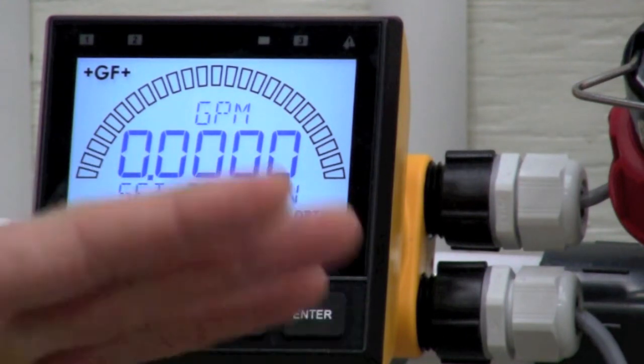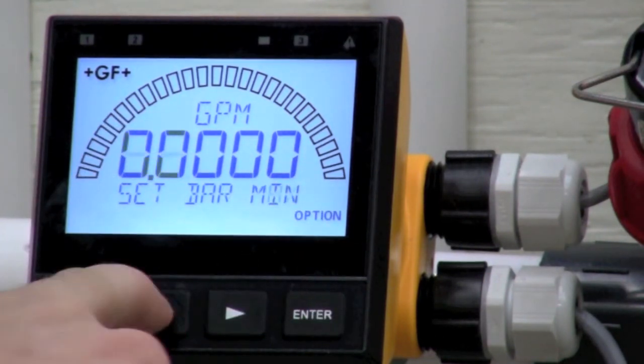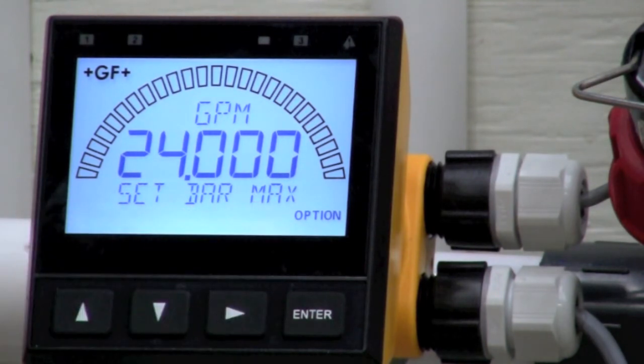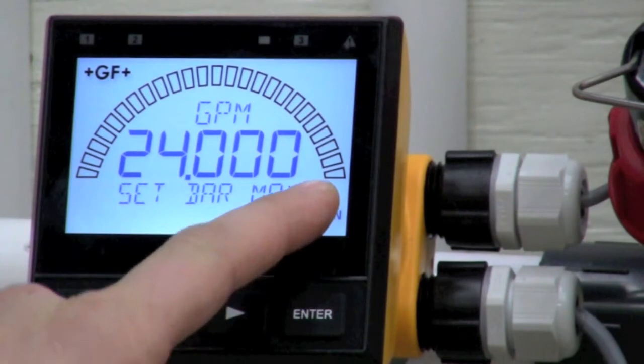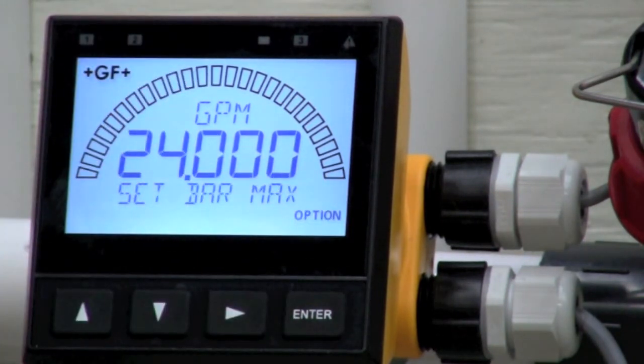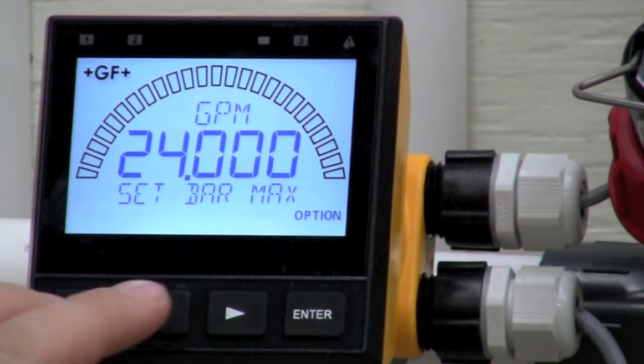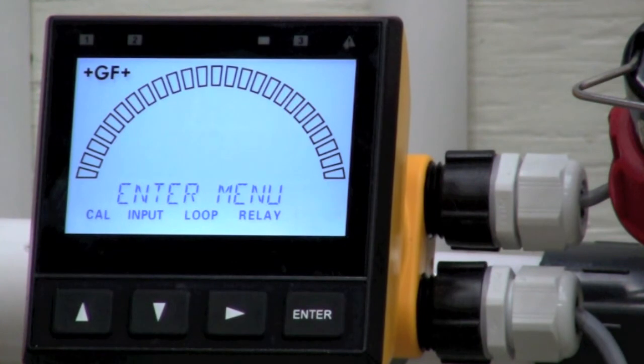I have this set for zero. Maximum bar, 24. That's where my set point is. Now this will not peg until I hit 24 GPM. However, my 4 to 20 will still peg once I hit 15 GPM. That's how you set that. I'm going to hit back out on this.